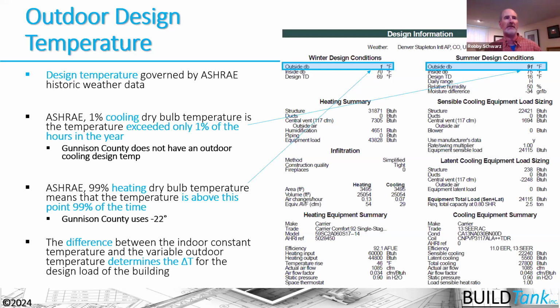But that changes when we get to the wintertime conditions here. And so the same kind of thing is happening here. It's basically saying that in the wintertime, we want to pick a temperature that isn't exceeded 99% of the time there. So the worst case scenario in Gunnison is -22. So we don't want to design for something that's colder than that, because it's only colder than that maybe 1% of the time during the course of the year. 99% of the time it's -22 or warmer there. So our worst case scenario would be -22.